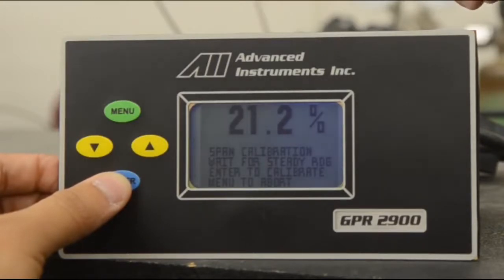You want to confirm that the reading is stable and take anywhere from 10 to 15 seconds to view the reading and confirm that it is not fluctuating. This is essential as you want a reading that is stable and correct on 20.9. Now, as you see, it went from 21.2 to 21.1, but is fairly stable now. Now we can press enter to calibrate.